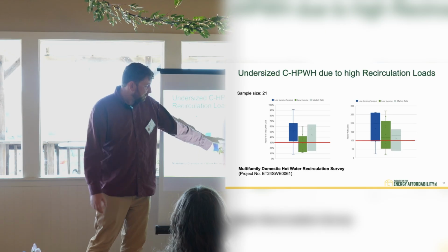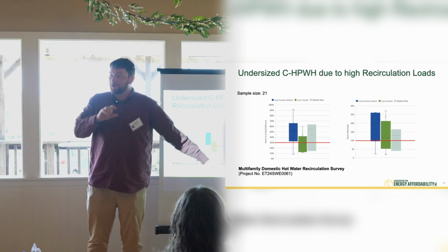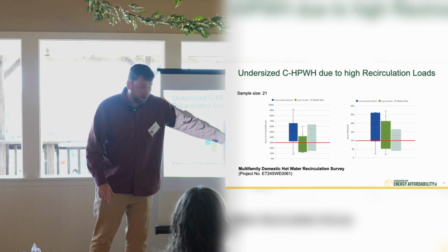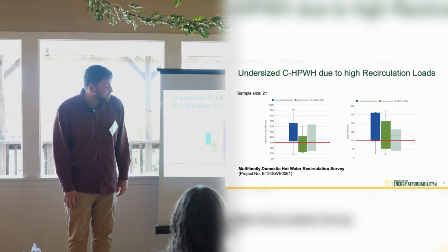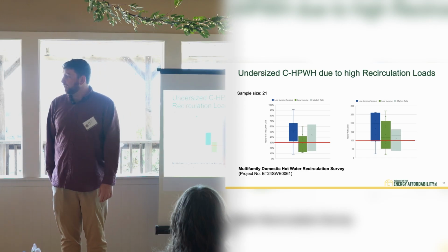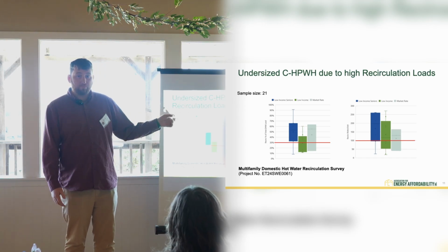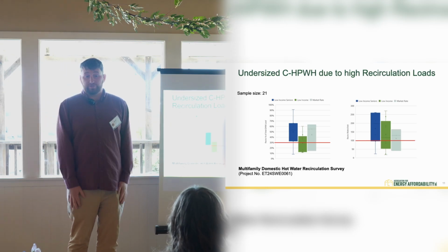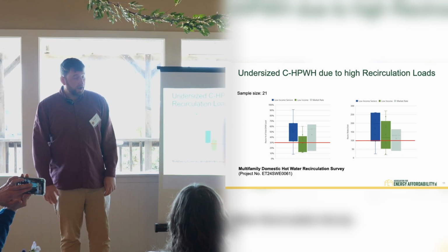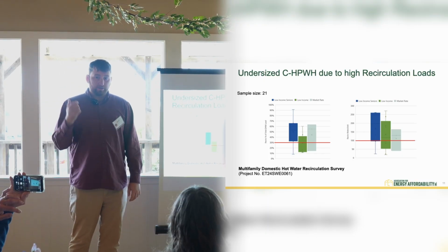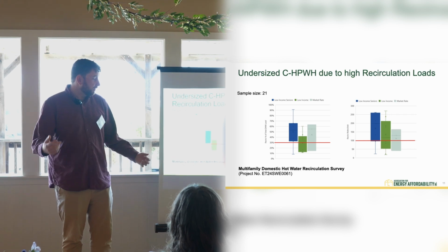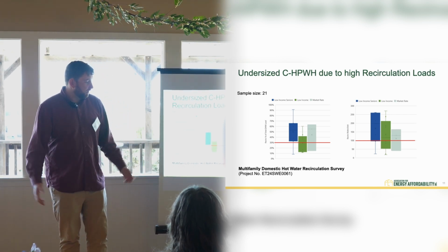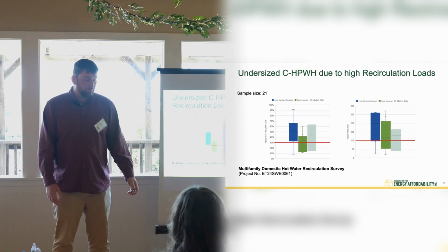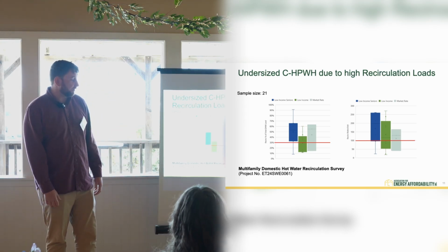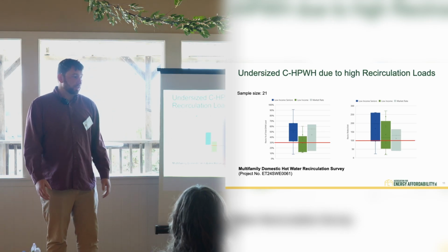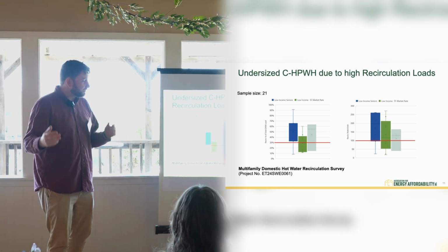And then in addition, sorry, Sean, but this is like the Ecotope 100 watts per apartment. If you compare that to the watts per apartment that we're seeing in our buildings, it's all over the map. And so this is why central heat pump water heater systems fail, is because we're not taking the time to actually monitor the distribution system and improve the distribution system. We've seen really, really high savings by improving imbalance, removing crossover. We've oversized all of our piping, which has increased heat loss. So these are all things that are critical to consider when you're installing a central heat pump water heater to avoid failure. And one black eye of a central heat pump water heater is like 10 steps back for affordable housing developer. And so we really want to avoid that.